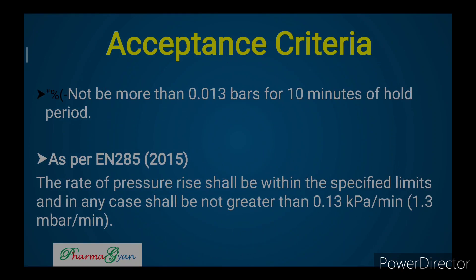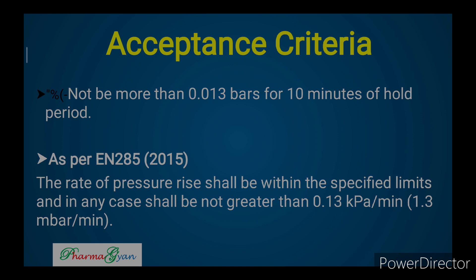Acceptance criteria: not more than 0.013 bar for a 10-minute hold period. As per EN 285-2015, the rate of pressure rise shall be within the specified limits and in any case shall not be greater than 0.13 kPa per minute, or 1.3 mbar per minute. So according to EN 285-2015, the acceptance criteria for vacuum leak test is that pressure rise should not exceed 0.13 kPa/min or 1.3 mbar/min — below this is acceptable, but beyond this the test fails.